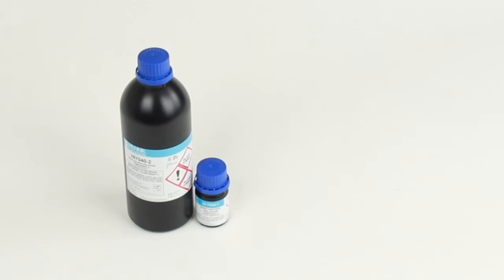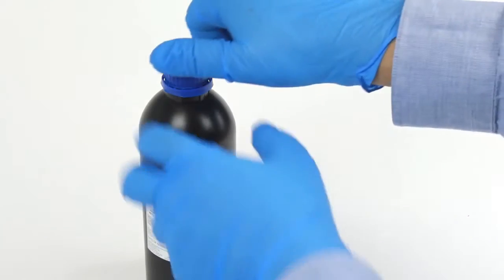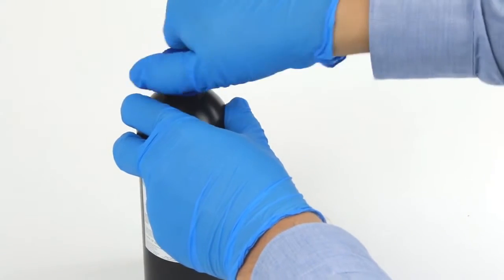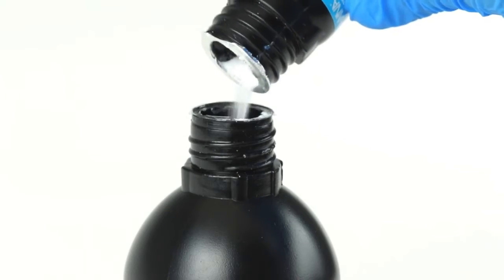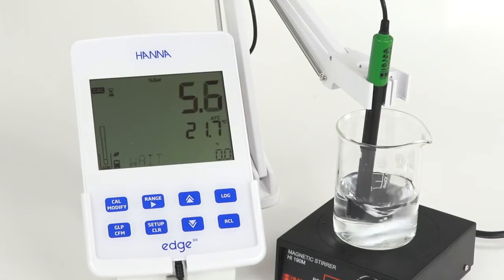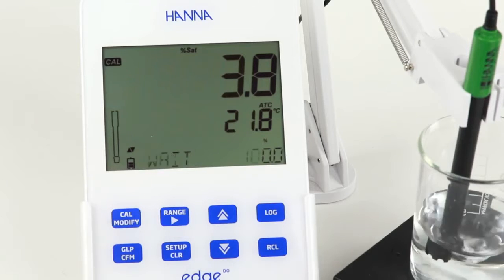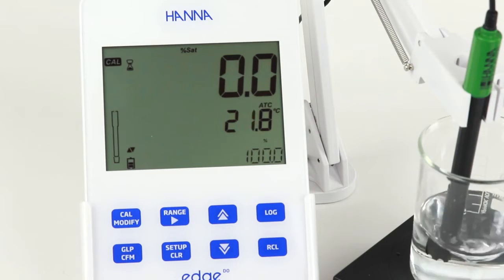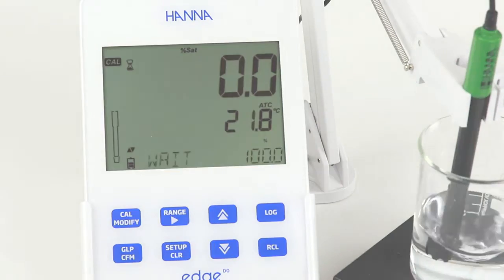To calibrate at 0%, the zero oxygen solution must be prepared. To do this, simply mix the two supply components. The solution will be valid for 1 month. For calibration at a second point, simply submerge the probe in about 60 milliliters of zero oxygen solution. Be sure to use a magnetic stirrer for best results. Once the reading is stable, press Confirm to accept the calibration point. The meter automatically saves the second point and returns to measurement mode.